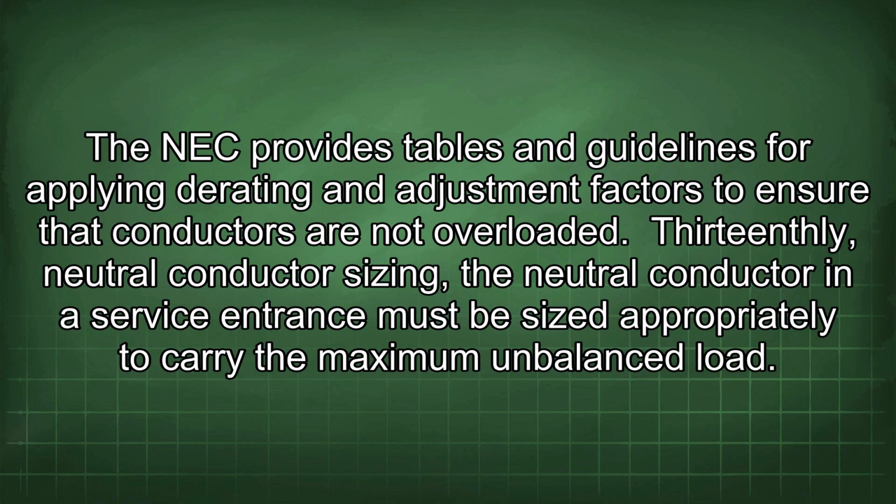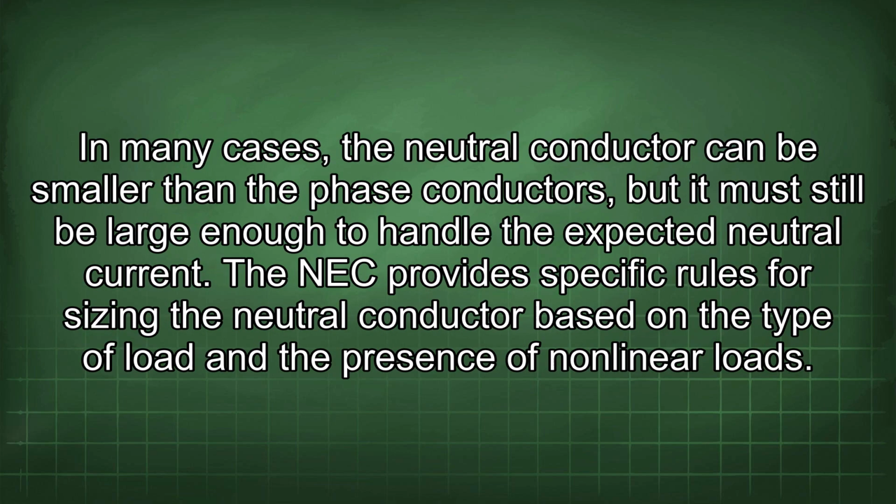13thly, neutral conductor sizing. The neutral conductor in a service entrance must be sized appropriately to carry the maximum unbalanced load. In many cases, the neutral conductor can be smaller than the phase conductors, but it must still be large enough to handle the expected neutral current. The NEC provides specific rules for sizing the neutral conductor based on the type of load and the presence of nonlinear loads.